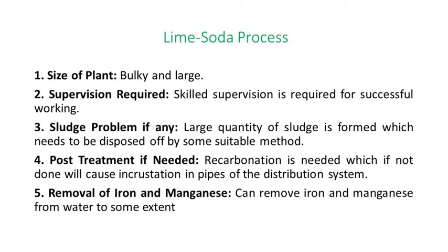A large quantity of sludge is formed in the lime soda process, so disposal of sludge is a very important problem. And in the zeolite process, no sludge is formed, and therefore there is no problem of sludge disposal. Next point, the post treatment required: recarbonation is a must after sedimentation and filtration in the lime soda process, and in the zeolite process no such post treatment is required after the removal of hardness. Okay, so in the lime soda process recarbonation, that is post treatment, is required, and in the zeolite process no such post treatment is required.